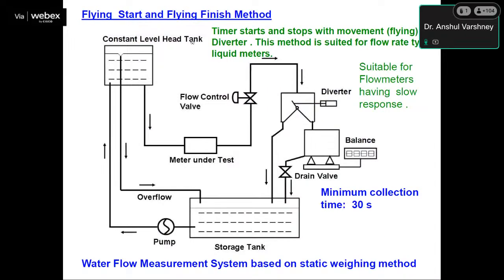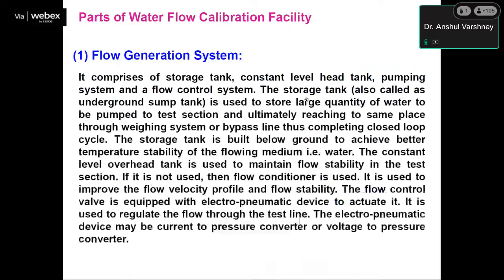However, in flying start and flying finish, the timer starts and stops with the movement of the diverter. This method is suited for flow rate type liquid meters and is suitable for flow meters having slow response. The minimum collection time for this method is 30 seconds as per ISO 4185.